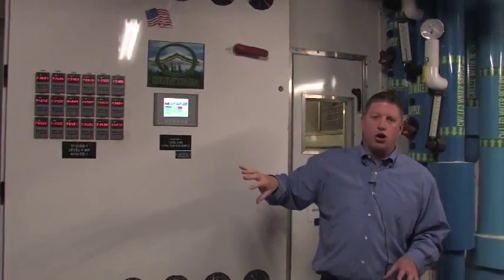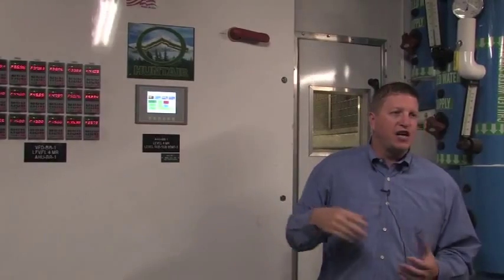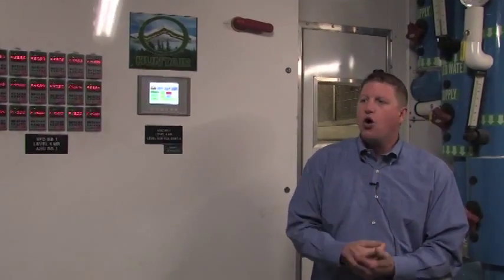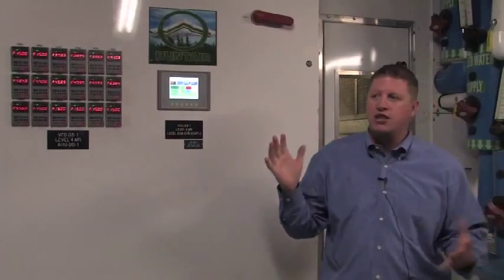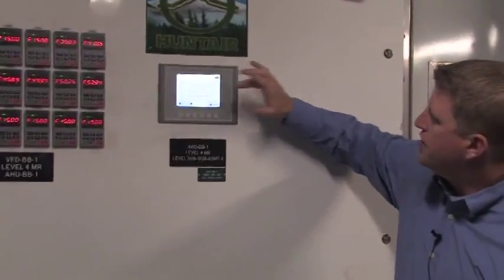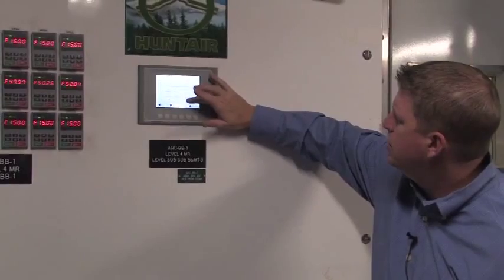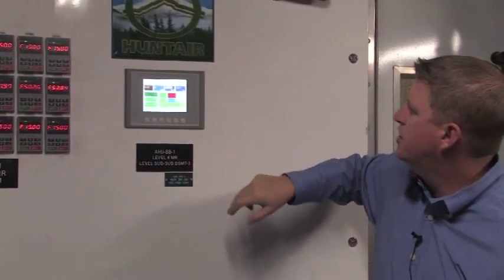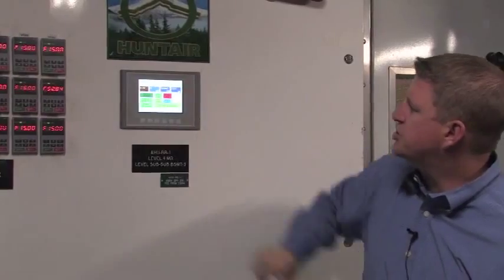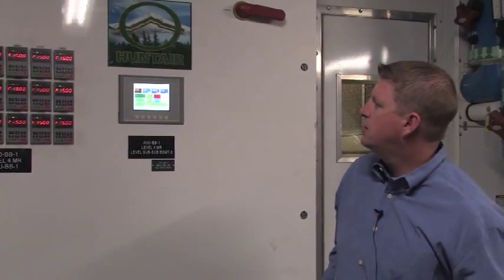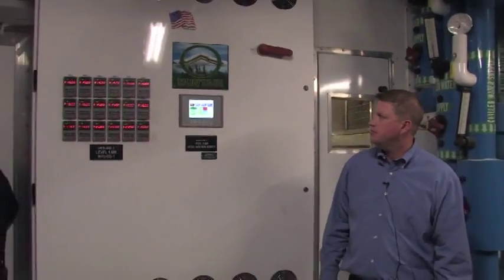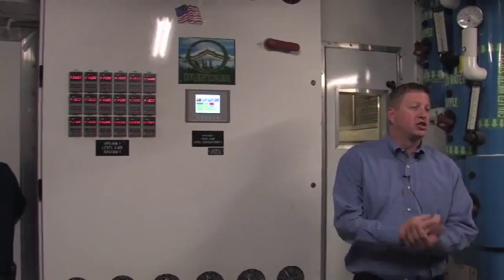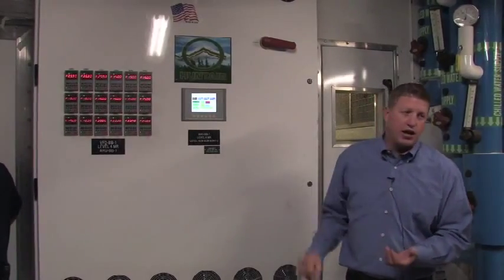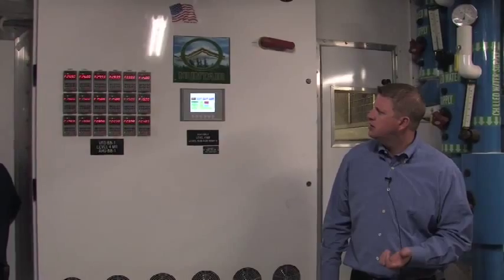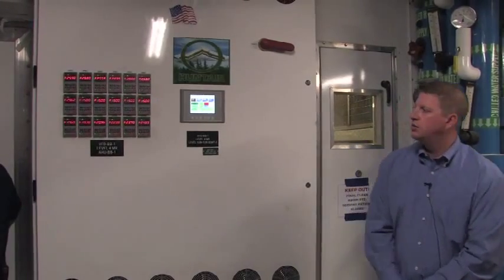Now, if I want to control to CFM, let's pick a number, 20,000 CFM. I'm going to go to enter CFM. I'm going to put in 20, hit enter, hit global start, and it's going to go and hold 20,000 CFM. Now, like I said, some people like to control to hertz. So I'll do that next. We'll let it get up, let it hold, settle out.